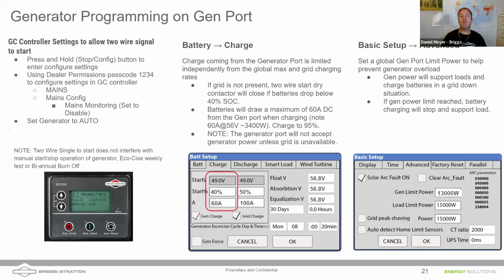But the first thing on the far left is when we have a Briggs & Stratton generator, right? If a generator starts, everybody understands that it's going to provide power to the house. But when a generator is sitting there in standby waiting for an outage, we have to feed power to that generator. Why? Because we've got to keep the starting battery in the generator itself, that little lead acid battery, on a battery tender, right? We've got to keep it charged. If we have any cold weather kits in our generators, we've got to keep those powered. So we're feeding power to the generator all the time.